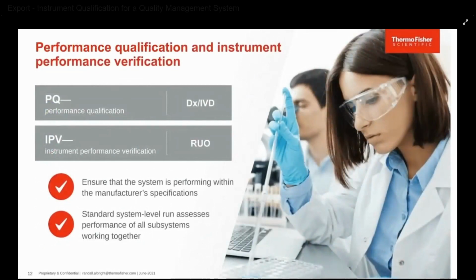Final component of a qualification is performance qualification or instrument performance verification. Remember, Thermo Scientific uses PQ for its DX or IVD instruments and IPV for its RUO instruments. By definition, the performance qualification or instrument performance verification will establish confidence that process, equipment, and ancillary systems are performing to the manufacturer's recommendations by demonstration with objective results. Now, this might be a bit confusing. The most common understanding of a PQ or performance qualification is the established limits and specifications for the entire workflow or process, including equipment, instruments, and software. In the case of Thermo Fisher Scientific, the instrument hardware qualification, the PQ component, is focused on the workflow of our instrument hardware, not the larger workflow or process PQ that the instrument is being used in.